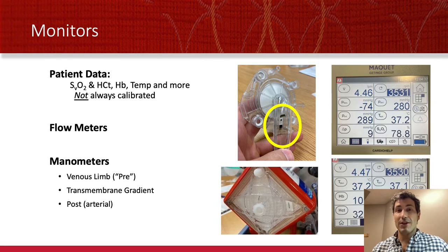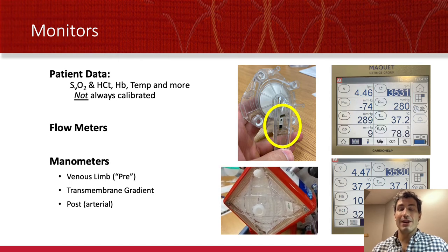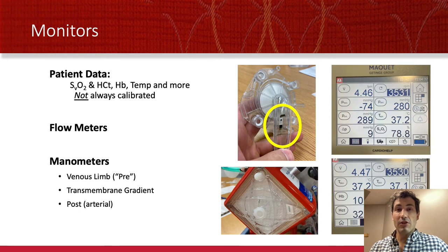These are manometers. We look at the venous pressure — how much negative pressure does it take to pull blood from the patient to the ECMO circuit? If you're really dry, hypovolemic, bleeding out, or if you have tiny little vessels, you might pull the vessel walls into the ECMO cannula. All those situations are going to give you a negative pressure — kind of like trying to drink water through a tiny straw; as you suck in, your cheek's going to suck in. That negative pressure is called the suck pressure. We want it to be as low as possible, ideally under 50, under 75 critically, and when you go more negative than minus 100, be very afraid that you could have a suction event where you have no blood to suck through and the cannulas stop taking in blood.